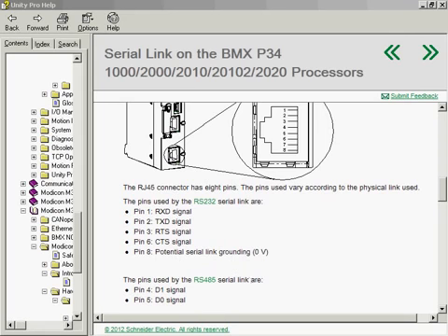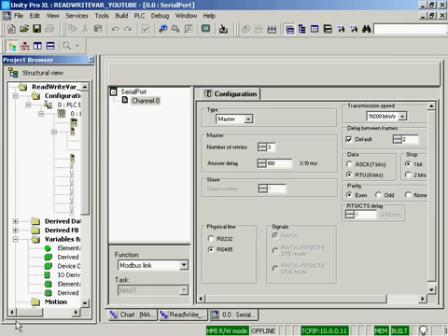We have our PLC programmed, the serial port on the PLC programmed as a master, 1 second timeout, RS485 2-wire, 19.2K baud, 8-bit RTU, 1 stop bit, even parity.